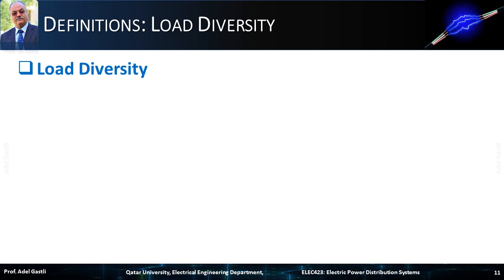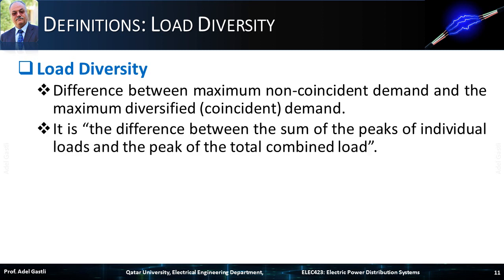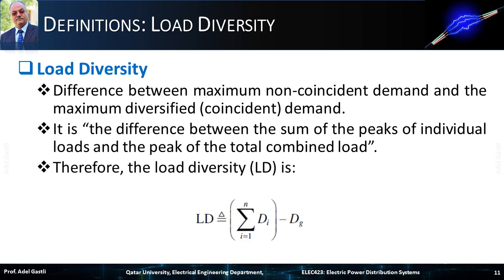Now let's define the load diversity. It is the difference between the maximum non-coincident demand and the maximum diversified demand — in other words, the difference between the sum of the peaks of individual loads and the peak of the total combined load. The load diversity is given by an equation where n is the number of connected loads, DI is the individual peak demand of each connected load, and DG is the peak of the combined load. Note that load diversity is not a factor but is usually expressed in kW, kVA, or amperes.